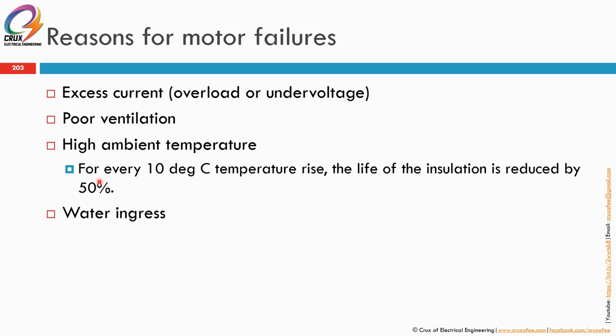So the rule of thumb is for every 10 degrees Celsius temperature rise, the life of the insulation is reduced by 50%, okay? And last but not least is also due to water ingress. This normally happens within the motor terminal box or within the motor itself.